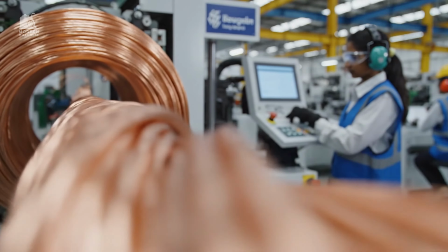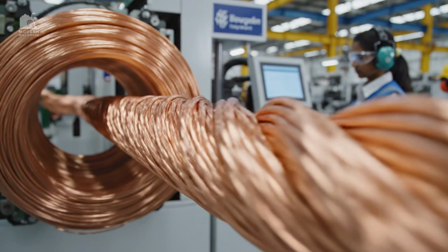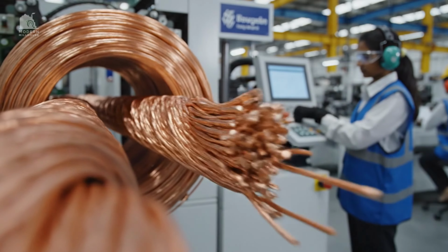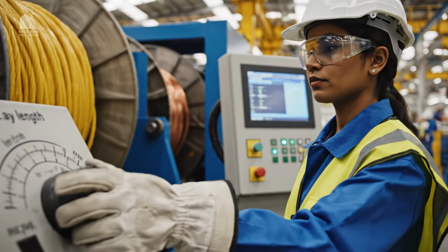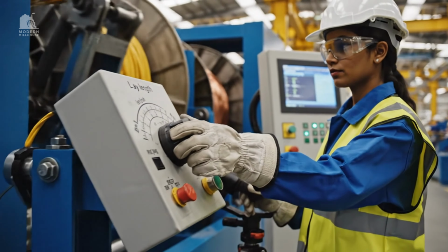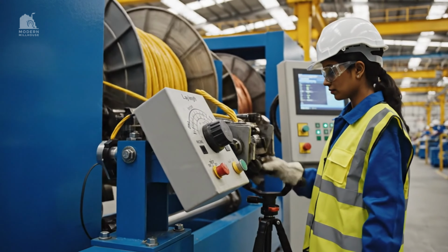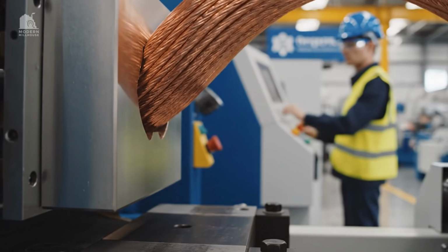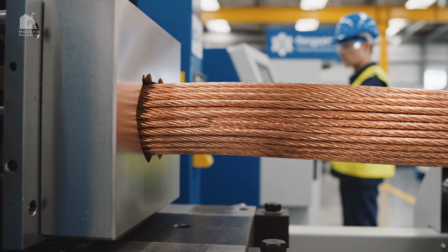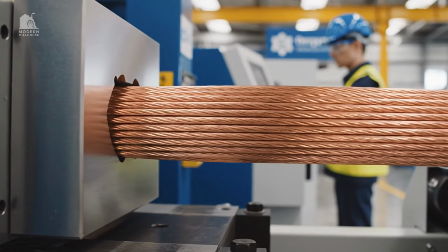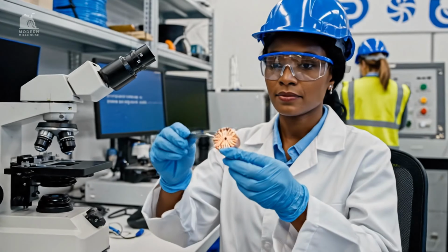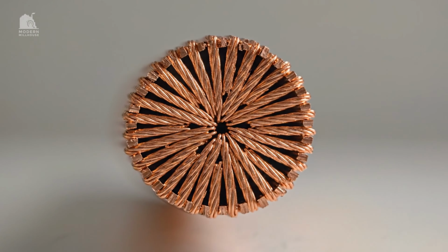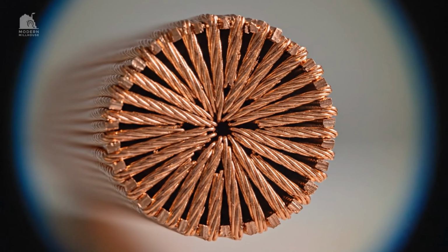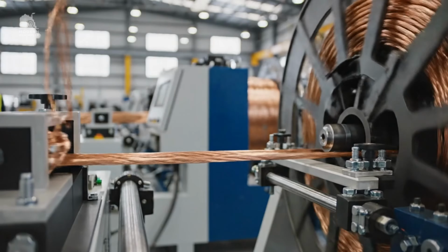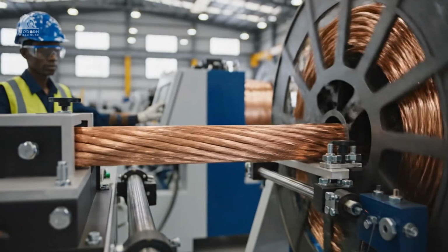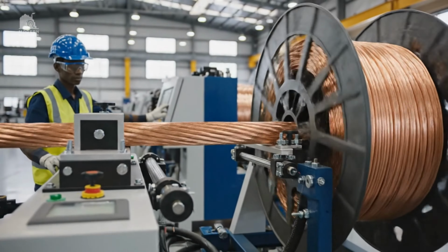The twist pattern, called lay, affects diameter, flexibility, and how the conductor behaves under motion. Changing lay length changes the helix angle, tuned to the cable's final application. Some conductors are compacted to reduce air gaps and create a tighter, rounder shape. Cross-sections confirm the strand count, packing, and symmetry before insulation is added. The stranded conductor is rewound for extrusion, where insulation will be applied at high precision.